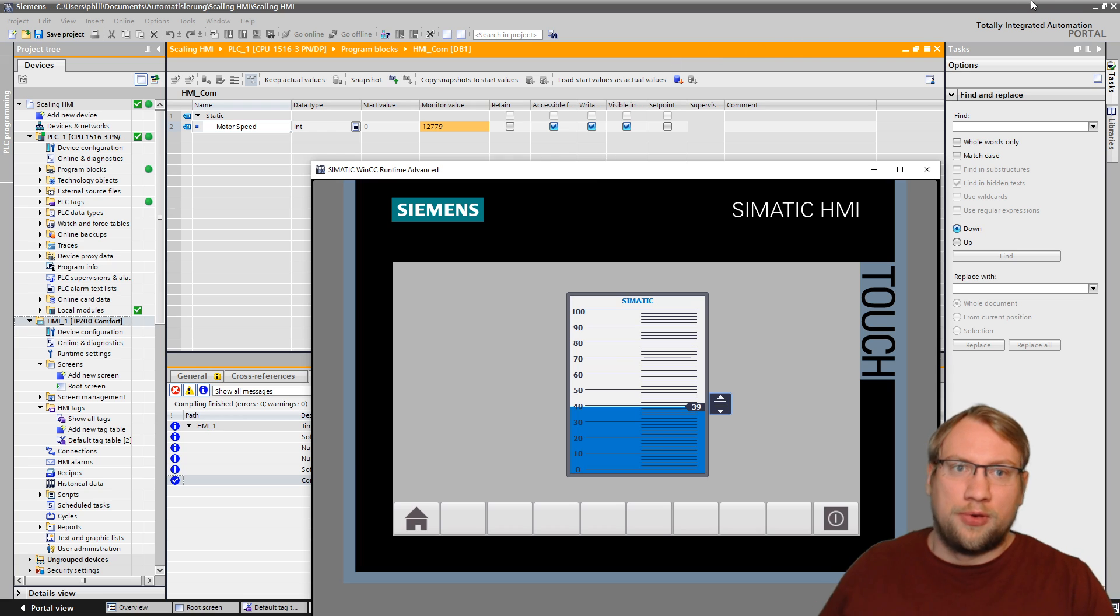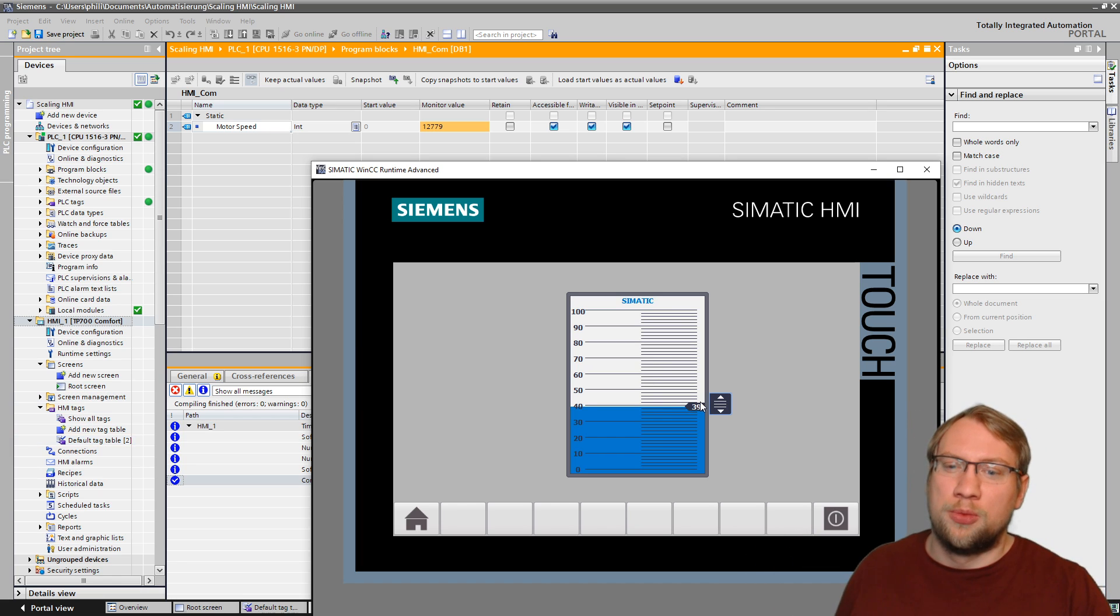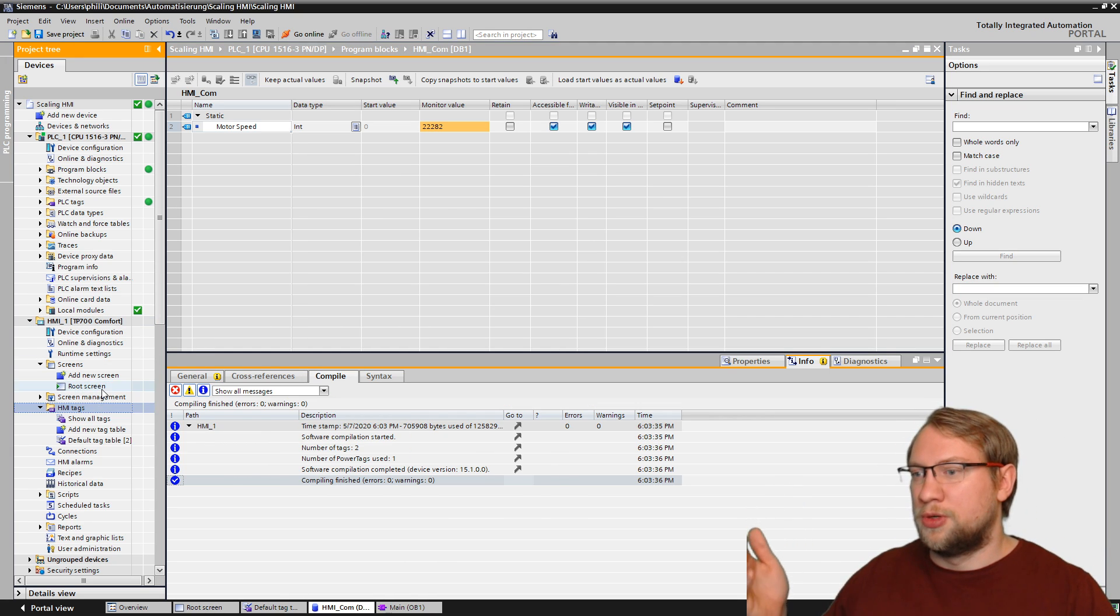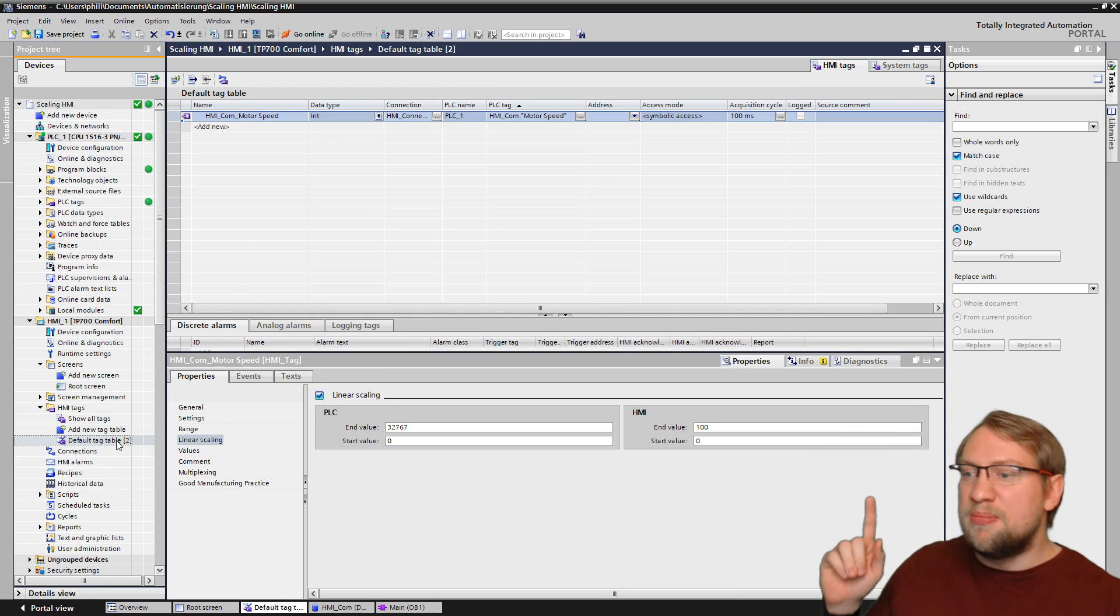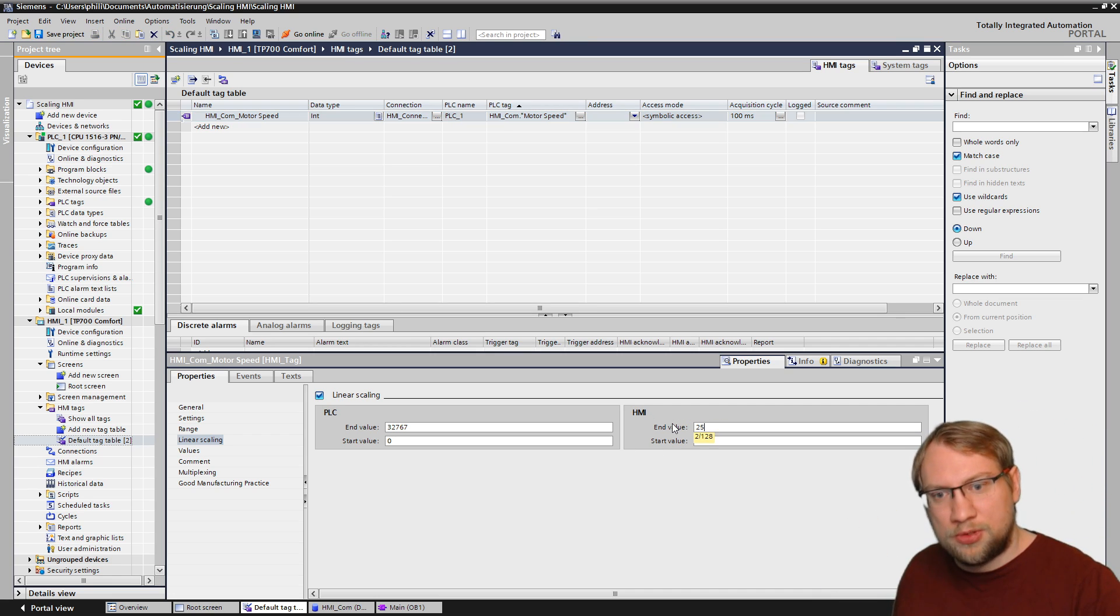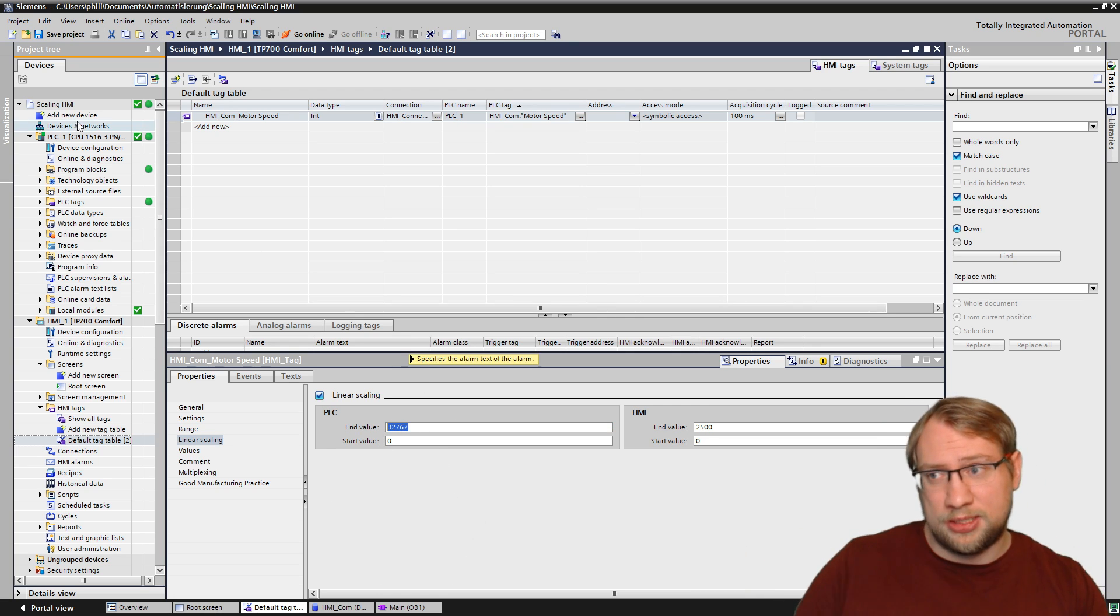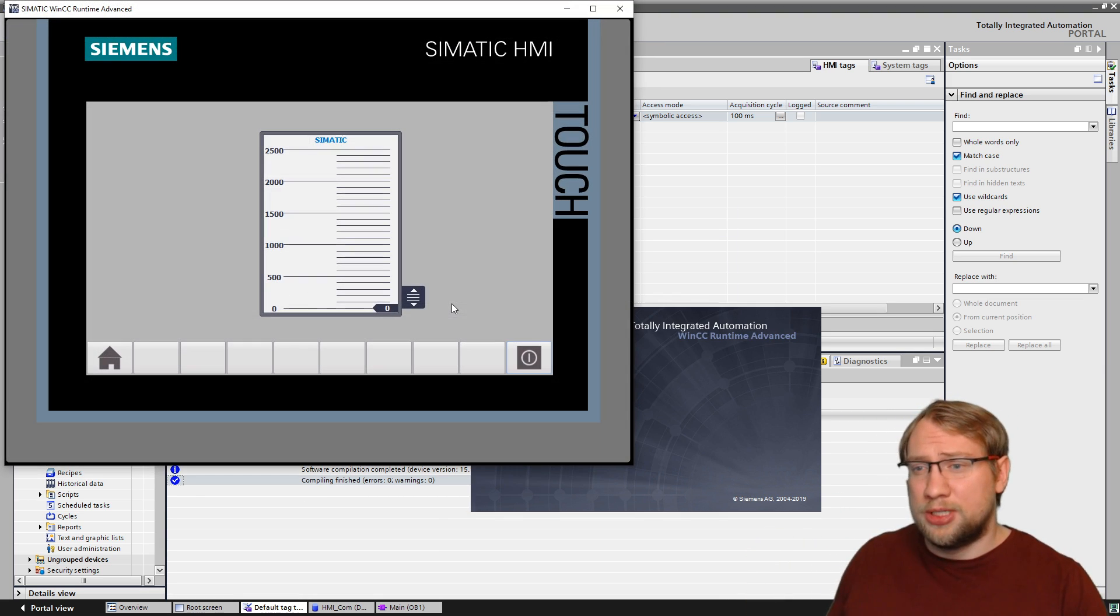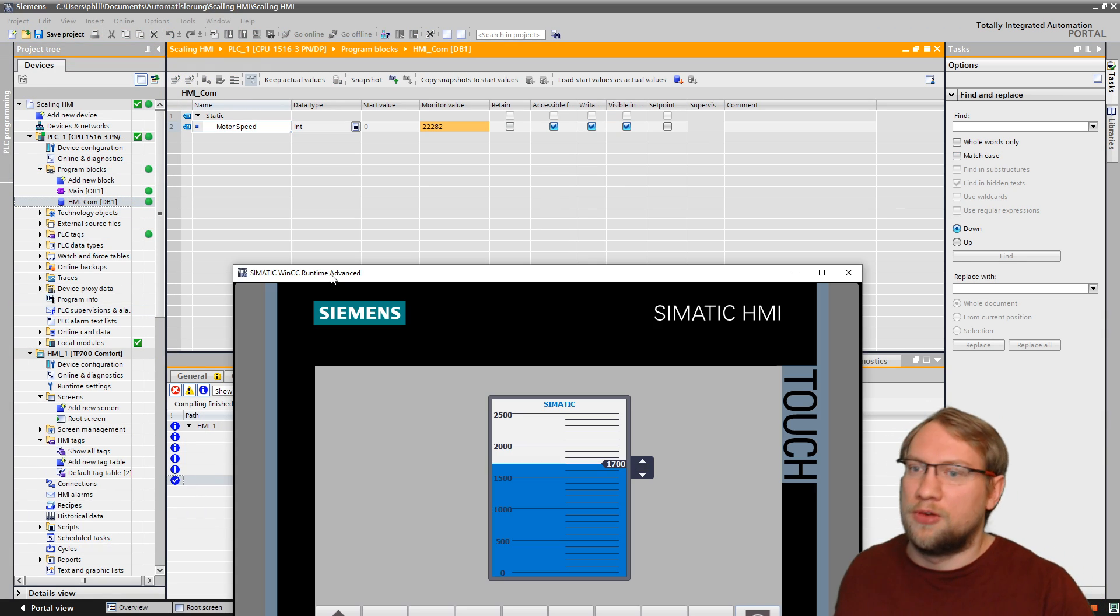Now, if you would like, for example, hey, you want to control a motor speed, right? You want to control the motor speed directly. And let's say your motor speed is not just 100 or it is 2,500. So, what do we do? I go to my root screen here. I change the display here. The maximum should be 2,500, right? And then, I go also to my variables in my HMI, right? That's HMI variables. And I just say, on the HMI, if it says 2,500, that is the same as 32,767 on the PLC. That's it. And now, we're talking about revolutions per minute, RPM, right? Pretty simple. Could be anything else, right? That's just scaling. Very simple way of scaling.